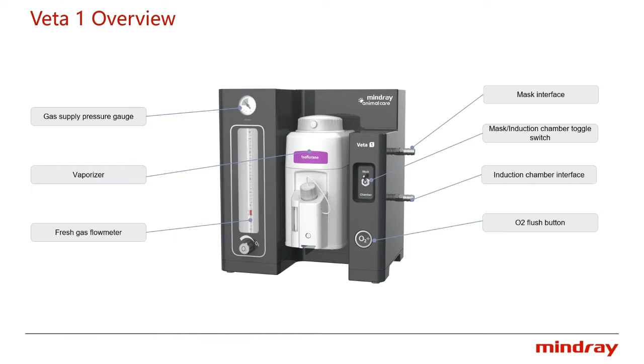And this page shows the configuration of Veta 1 and its accessories. The main unit is tabletop with two channels. One is for mask, one is for induction chamber. The flow meter here is a mechanical one. The flow range is from 0 to 4 LPM. And also the vaporizer here, we have one vaporizer fixed. We could choose either isoflurane or sevoflurane.